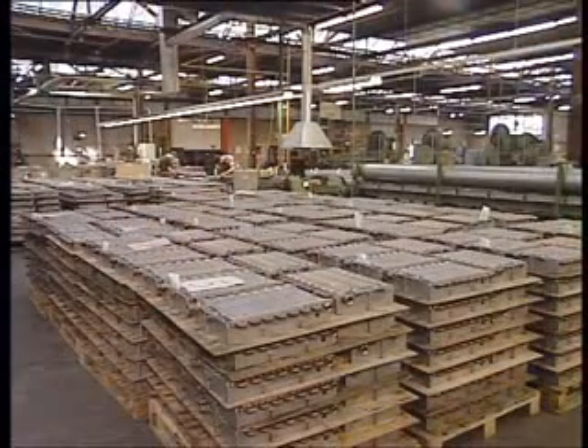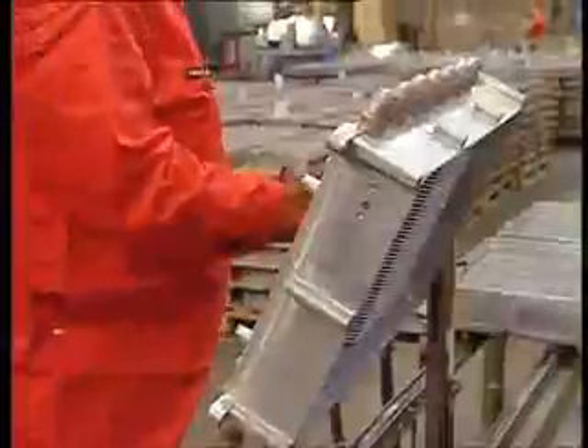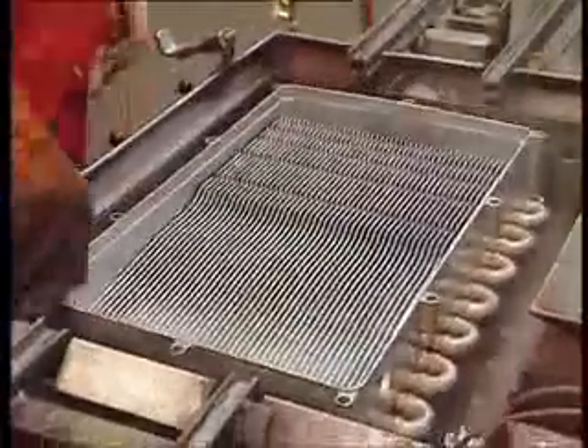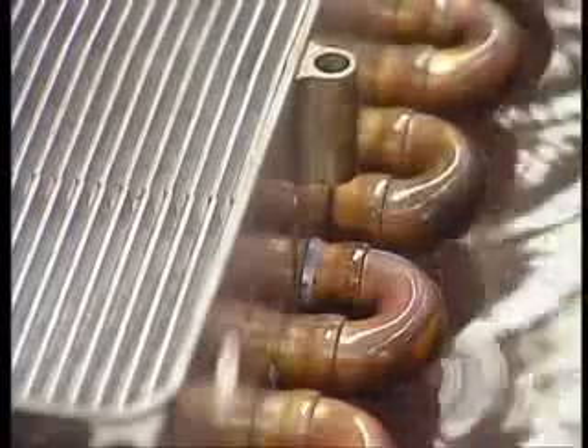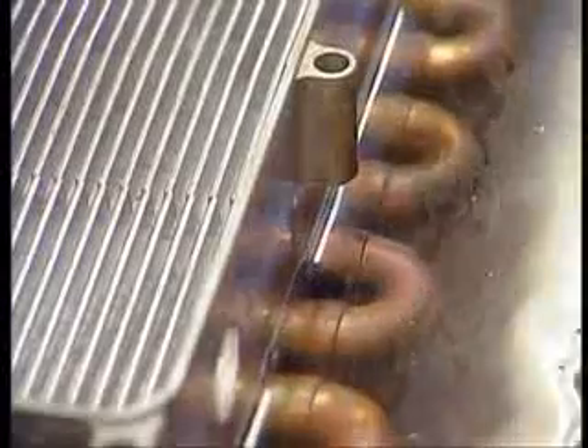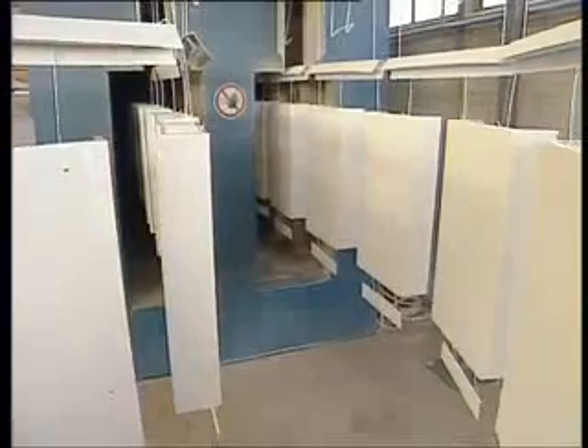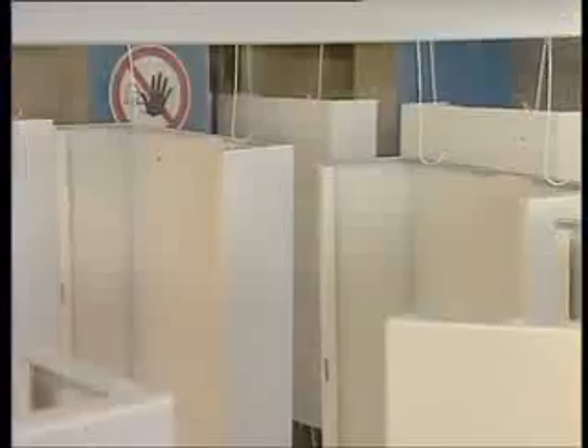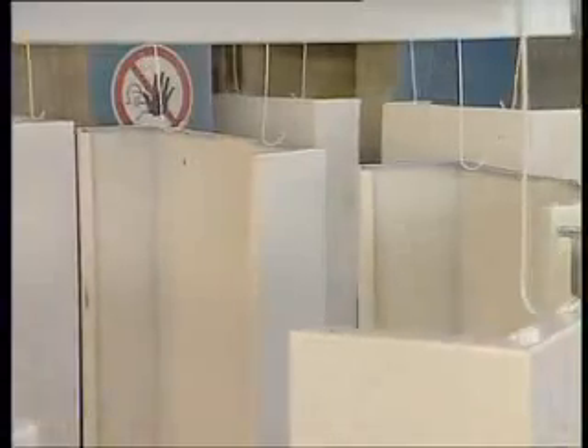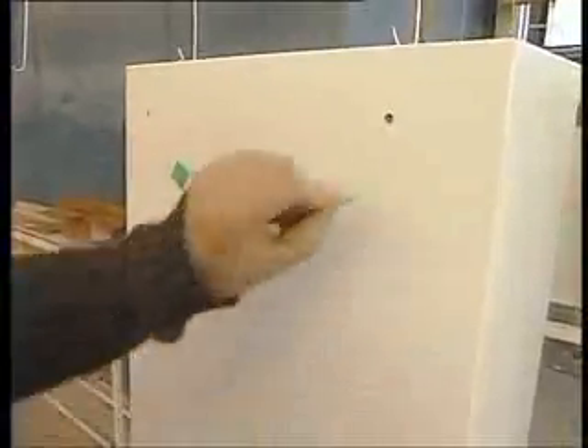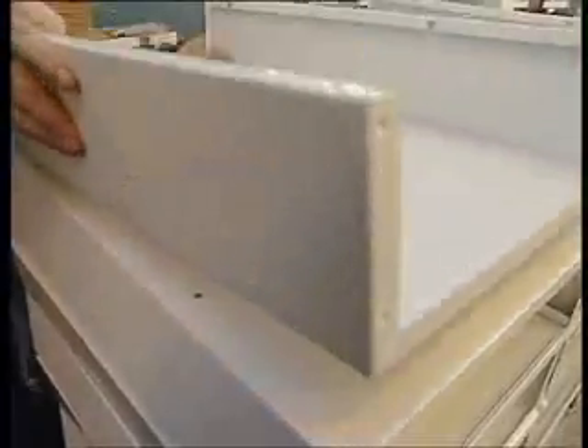The unique design that's proved itself in practice can still provide surprises. It's become more and more clear that the double heat exchanger has many advantages compared to the traditional systems. A considerable saving in energy consumption is realized by the high performance of the tap water. The most modern electronics which control the boiler are provided with a switch mode power supply, ensuring that no so-called standby losses occur. This also distinguishes the Combi compact condensing boilers from their competitors.